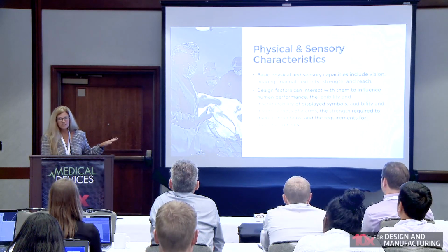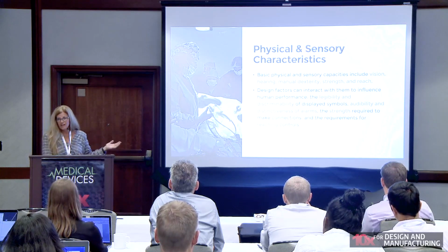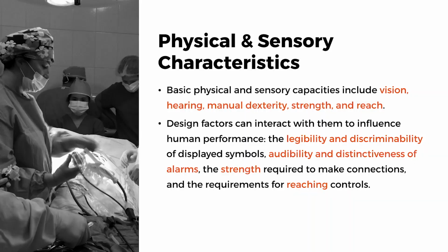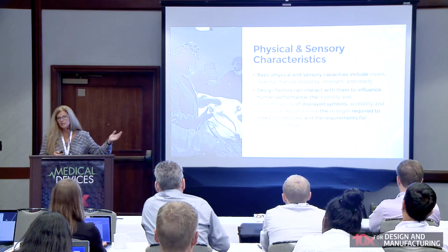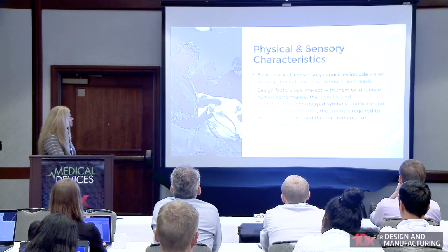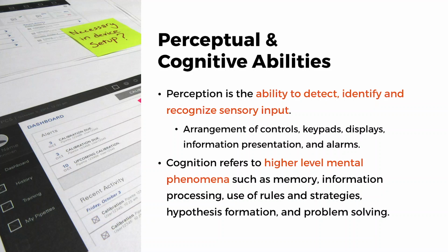I find that element of design to be the easiest. There's a great standard called AAMI HE75. It has all of that in there. That's the easy wins. What's more difficult are knowledge-based tasks, cognitive tasks where we are having to remember something. And that gets to the legibility and the discrimination. How do I hear an alarm? Can I hear an alarm over the top of what else is going on in the room? I just demonstrated for you all of the complexity of the devices that are in the room. So how does one alarm sound versus another alarm? Can I provide more cues to those alarms? Can there be a visual with that auditory signal? And that gets to perceptual and cognitive abilities.